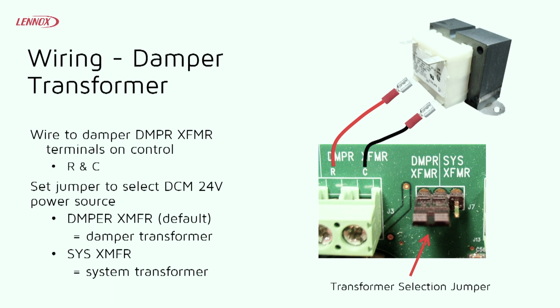So you have your damper transformer. Again, this is the jumper pin I was talking about, where you can select here whether you want to use the damper transformer or the system transformer to power the zone board and the dampers. Typically we'll just leave that at damper transformer because we'll have a separate one tied in.